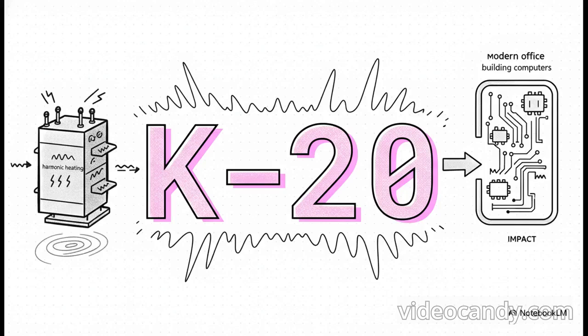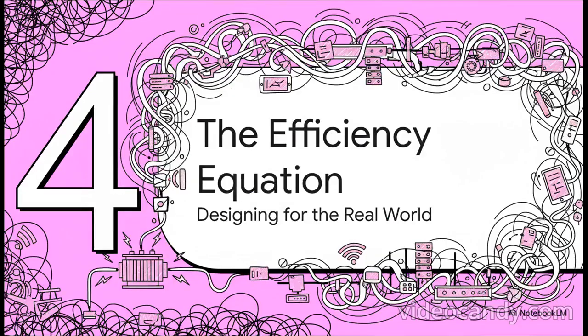So what does that actually mean in the real world? Well, for a building filled with computers, servers, and modern electronics, you don't just need a slightly better transformer. You might need one with a K-factor of 20. That's not a small adjustment. That is a transformer specifically built to withstand 20 times the harmonic heating effects. It's a staggering number that really shows you just how much our digital world has stressed the old grid.